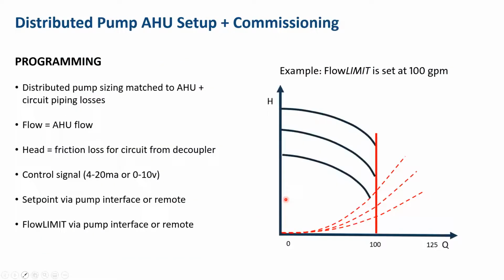The setup for this, to sort of finish it out, we talked a little bit about distributed pump sizing is really just matched to the AHU, the air handler, or whatever the load is. So whatever the flow rate is for that terminal unit, that's the size pump we would select. The head requirement for the pump would be the friction loss from the decoupler or the bypass to the physical location of the pump itself. The control signals we just talked about, we'd give the pump a set point either via the pump's interface or via remote control. We have the ability to use our smartphones to see the control interface for the pump if it's in a high location or up in the ceiling, wherever it might be.